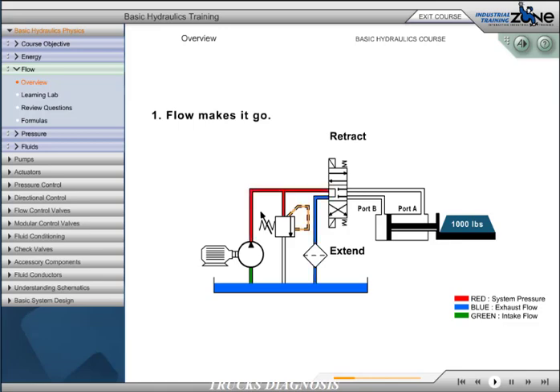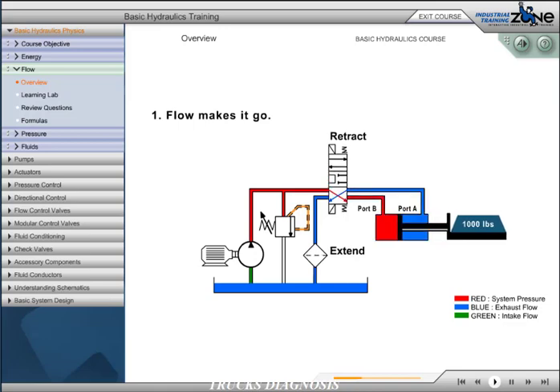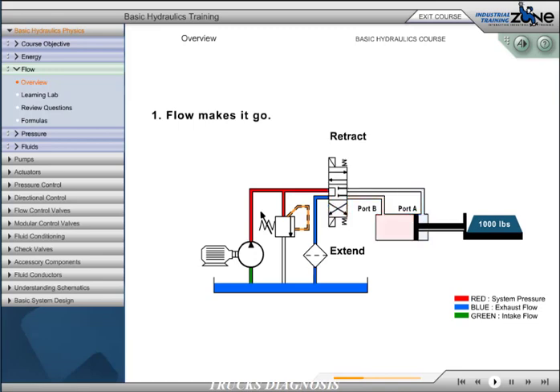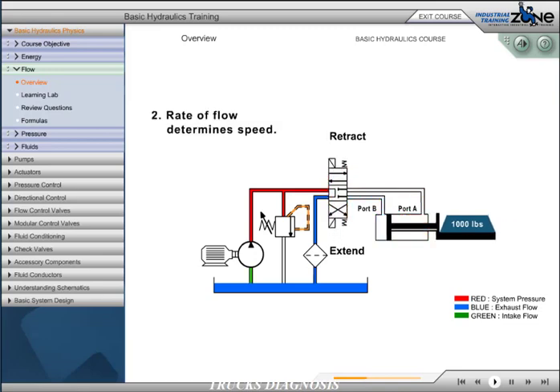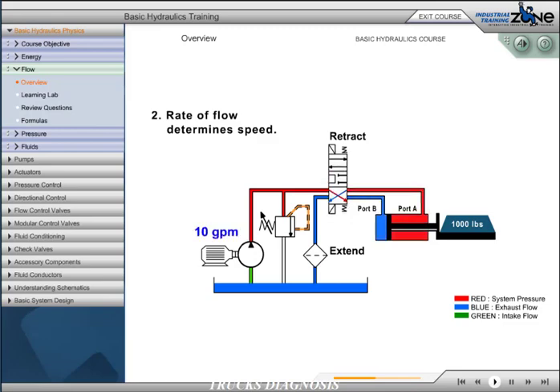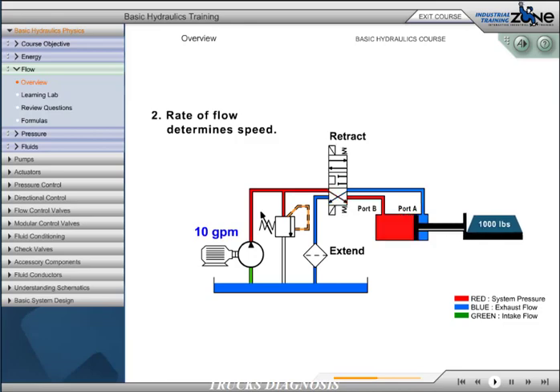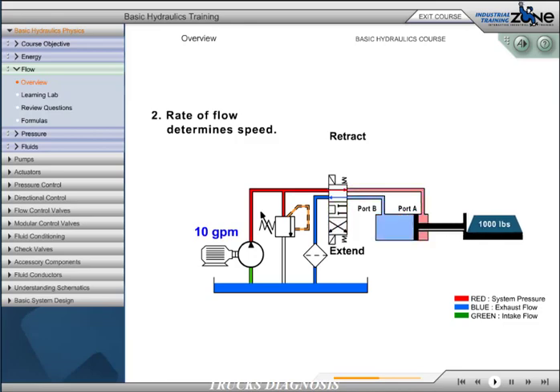This cylinder is retracted. It can extend only if there is flow into port B. Shifting the directional control valve will send flow to either extend or retract the cylinder. Principle 2. Rate of flow determines speed. Rate of flow is usually measured in gallons per minute or GPM. GPM is determined by the pump. Changes in pump output flow will change the speed of the actuator.